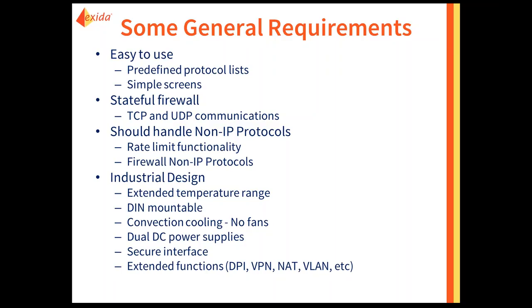Screens are simple and intuitive. They have stateful firewall functionality handling both TCP — connection-oriented — and UDP — connectionless. They should handle non-IP protocols, since many industrial protocols are not IP-based. They should have rate-limiting functionality and be able to allow or deny non-IP protocols. Many enterprise-level firewalls can't handle non-IP protocols and simply block or pass them by default, which is not acceptable in the industrial network arena. These devices are designed for industrial environments: DIN-mountable, convection cooled, extended temperature range.